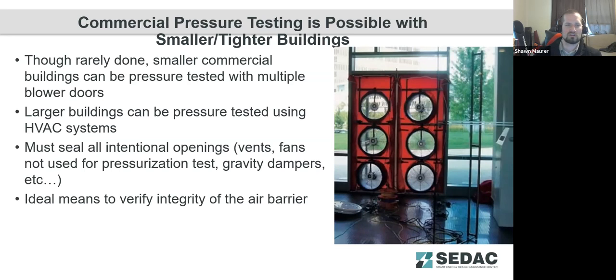And you convert that into a leakage per unit of envelope area, where the residential test is usually air leakage per square foot. For commercial testing, the test pressure is slightly higher. It's 75 pascals instead of 50 pascals. And the leakage measurement is based on the square footage of the exposed envelope. So you're not going to include envelope that's below grade, below the soil. It's only what's above grade and visible and open to the air that's being tested in this test.